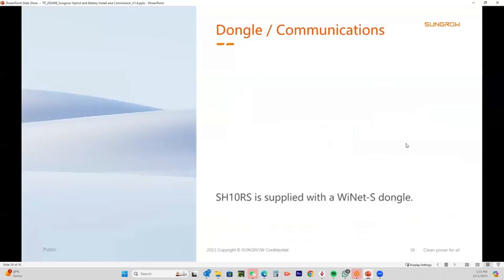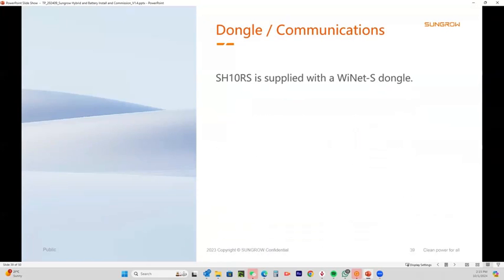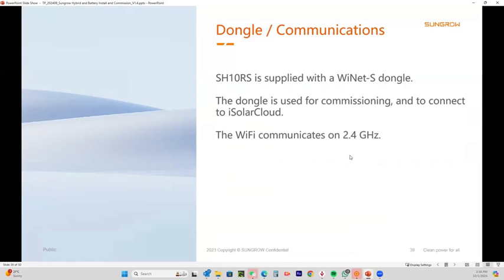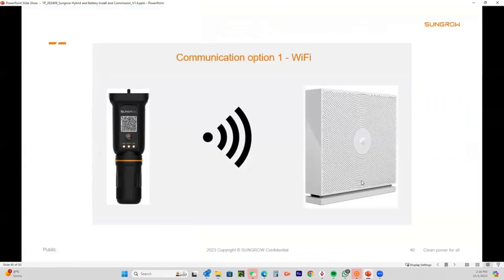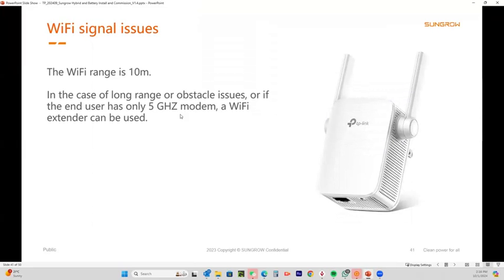Okay, dongles. Once you've got it all connected up, they're all connected with a WiNet-S dongle now. All the commissioning and connecting to the iSolarCloud is done through the dongle, and it's dead easy. It communicates on 2.4 gigahertz, so normally you use your phone, which I'll show you in a second, to connect to the customer's modem via Wi-Fi. If the range is more than 10 meters, or if the customer has a 5 gigahertz only modem, you can purchase Wi-Fi extenders. You can get dual band extenders that operate on 2.4 and 5. We've tested the TP-Link ones and they're quite good.